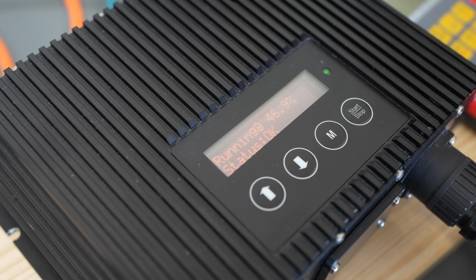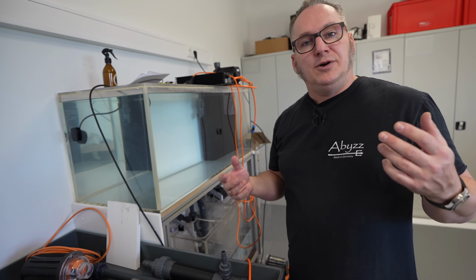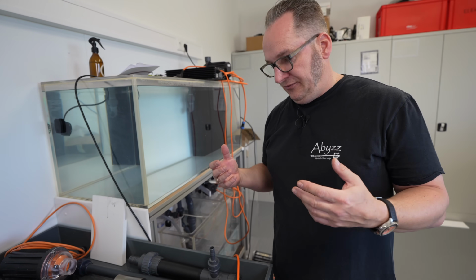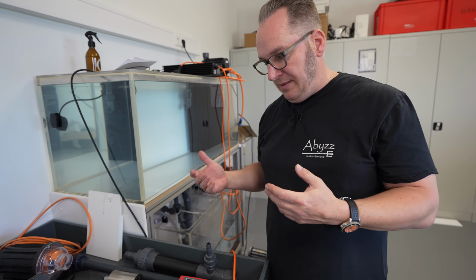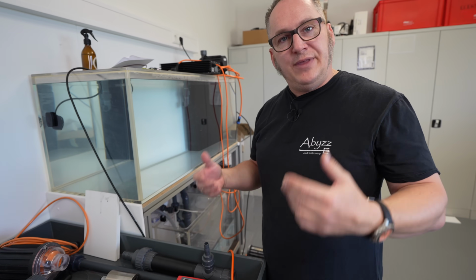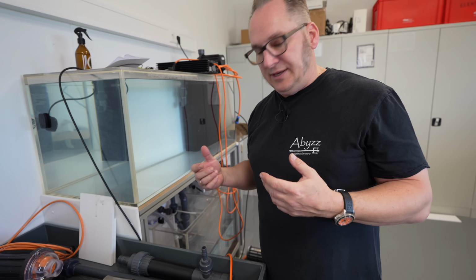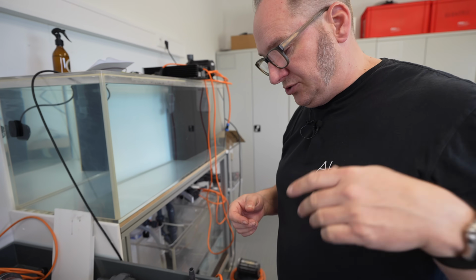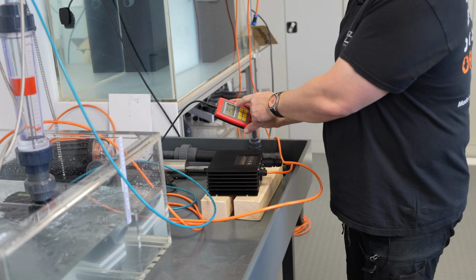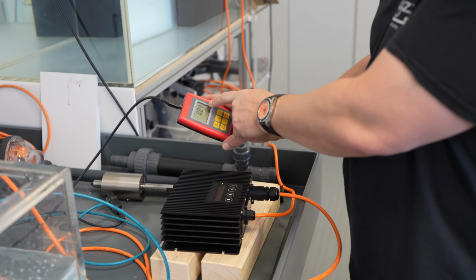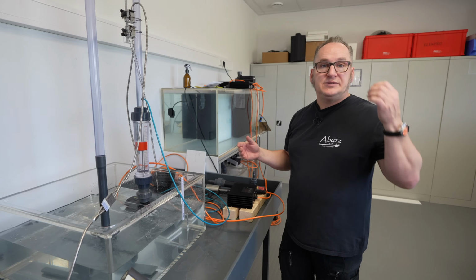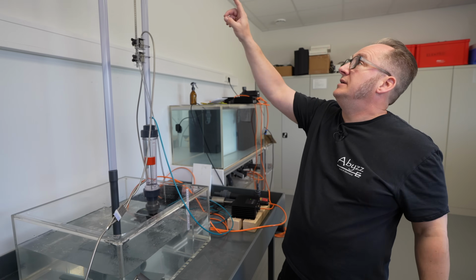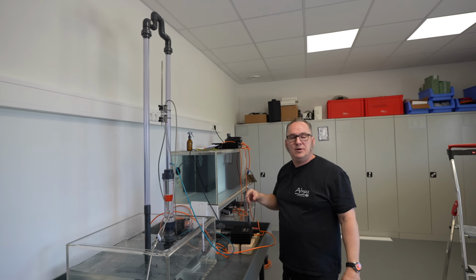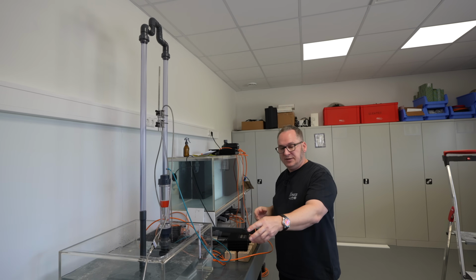That is because we're delivering less water. That's why we are also using less energy. So the physical work that is being done by the pump has become less, and that's why it's also using lesser energy. So when you're raising the head pressure, usually the power consumption drops to 42 watts. Notice that the head pressure though has changed significantly from 0.01 to already 0.04 on average. 4 times the head pressure by just having 6 90-degree hard elbows as compared to 2 soft elbows.